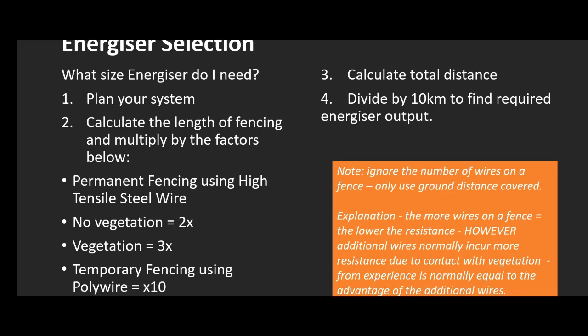When calculating length, you only need the distance of fence on the ground, not the number of wires. With a 3-wire fence, current flows through all 3 wires, so per meter resistance should be lower than a 1-wire fence. However, a 3-wire fence often has more vegetation contact, since the bottom wire is closer to the ground and more likely to touch grass and other vegetation. So as a rule of thumb, we work on total distance of fence rather than total wire distance, since the advantage of additional wires is usually lost to vegetation contact at some point in the season, keeping the method simpler.